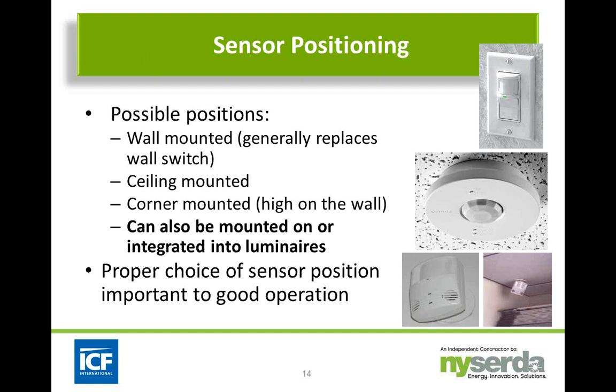They can also be mounted or integrated into the luminaires. I don't know if you've noticed lately, but you can see more and more options where the actual occupancy sensor is either mounted within or on the end of the luminaire. This is really a good way to get that to the space without having to add additional wiring. So you want to make sure you're choosing the right sensor for the positioning that you need for your particular space.